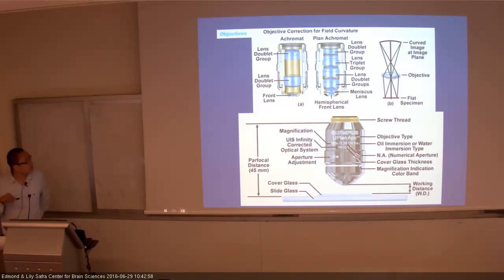Then the other things, like corrected system, aperture adjustment, magnification, color band, and cover glass thickness, are typically important for oil immersion objectives used for really high resolution observation of fixed tissues. For physiological measurements, they are not so critical. And water immersion objectives usually have a different design.